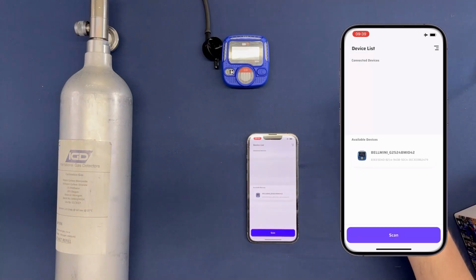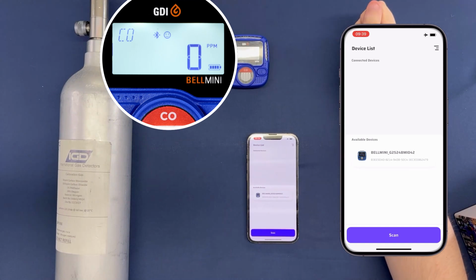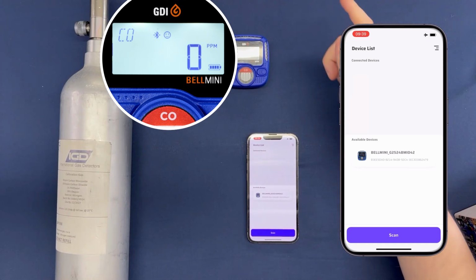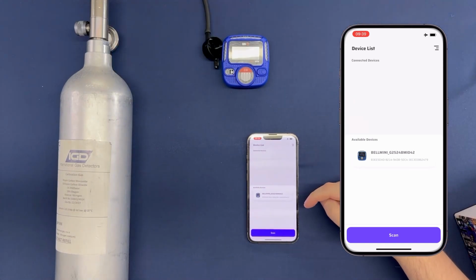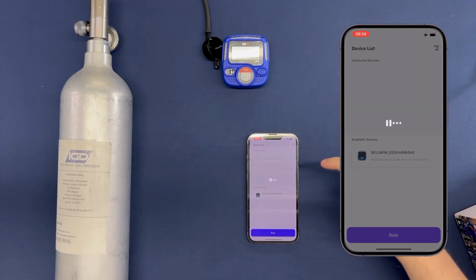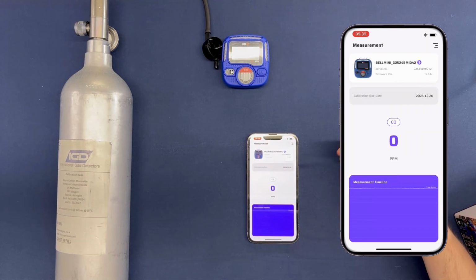So to begin with, as we discussed in the last episode, we show how to turn on the Bluetooth on your BELLMINI single gas portable, and as you can see here, we've already got Bluetooth turned on by the Bluetooth symbol that you can see at the top. And if we go into the BELLCONNECT app, we can then press scan. And once it scans the area, it will pick up the Bluetooth signal. And as you can see, our available device is shown here. So if we click on this, it will then start connecting with your BELLMINI single gas portable.